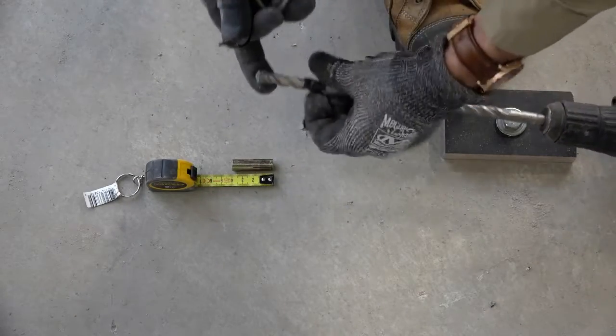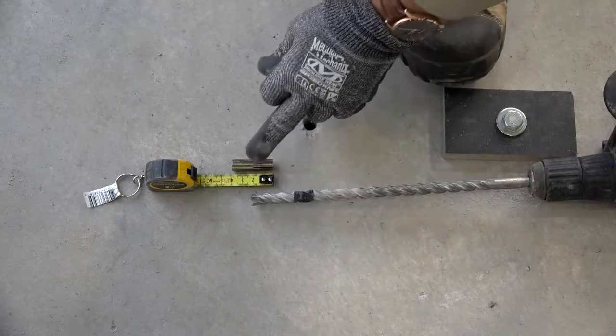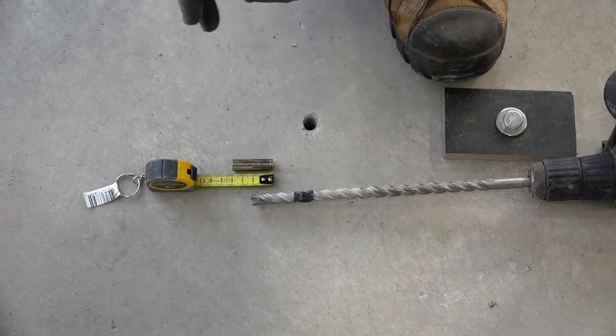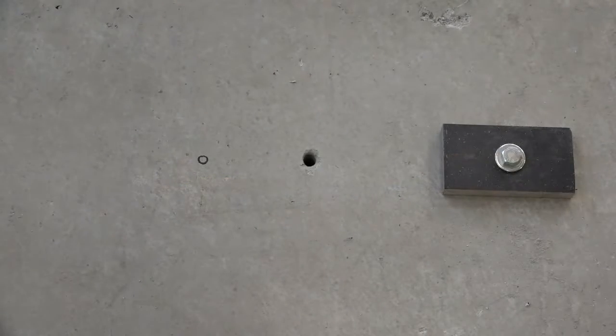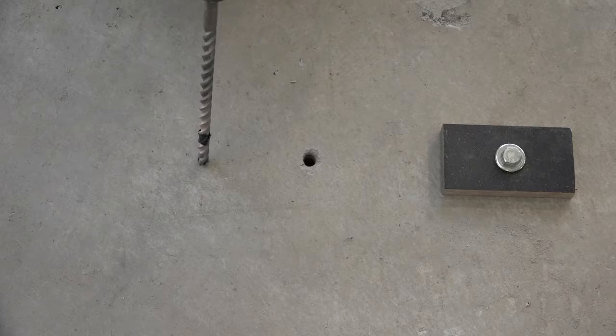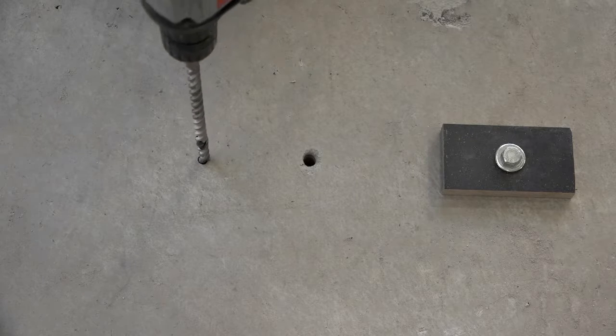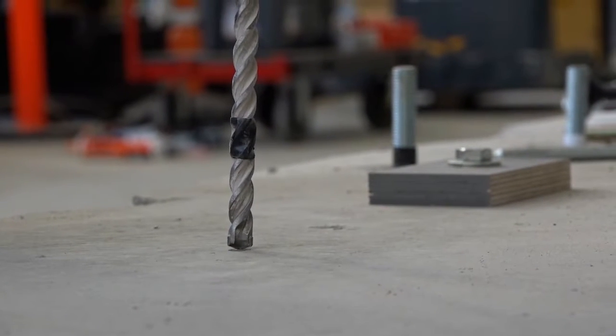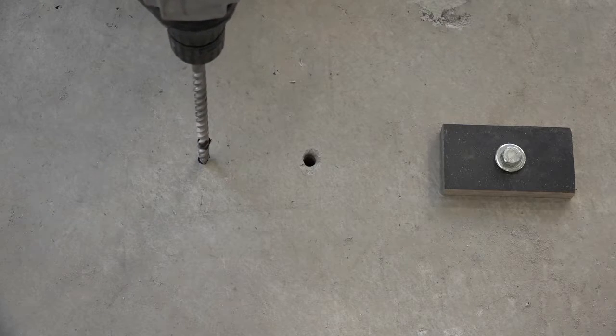So that when we do the installation and install the anchor into the drilled hole, the anchor will be flush with the concrete surface. Having marked the drill hole location in accordance with the project's documentation, place the drill bit, ensure alignment in both planes, and commence drilling.